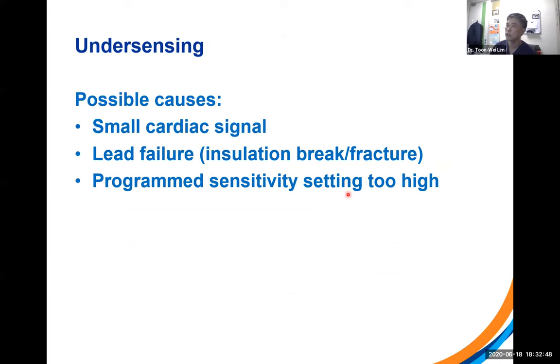So what are the possible causes of undersensing? Usually it's where the cardiac signal is too small, either due to some issue with the lead or some issue with the myocardium where the lead is implanted. It could be related to lead failure, either an insulation break or fracture, or the sensitivity setting has been set too high. In other words, the threshold for sensing has been set too high, and so the device is not actually sensing the intrinsic cardiac activity.